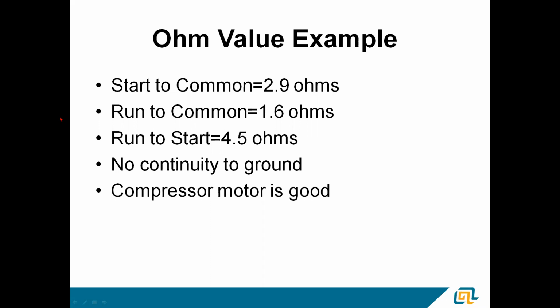Then you ohm from run to start. So you're ohming just the windings right through the compressor. It should add up to what the start and run winding worked out to be. So we had 2.9 ohms on our start winding, 1.6 ohms on our run winding, and we ohmed run to start and found we had 4.5 ohms. There's no continuity to ground. That compressor motor is acceptable. It should come up and run for you. Safe to energize at least.